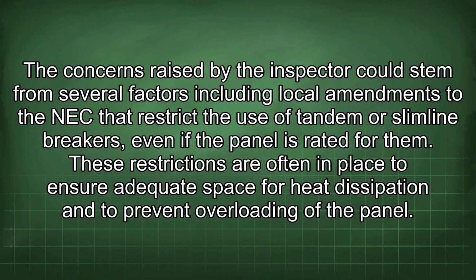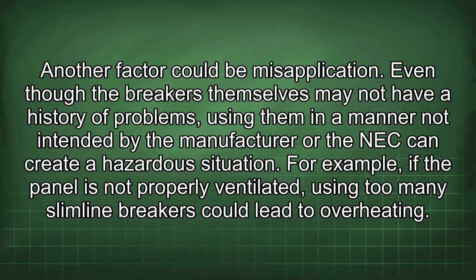The concerns raised by the inspector could stem from several factors, including local amendments to the NEC that restrict the use of tandem or slimline breakers, even if the panel is rated for them. These restrictions are often in place to ensure adequate space for heat dissipation and to prevent overloading of the panel. Another factor could be misapplication. Even though the breakers themselves may not have a history of problems, using them in a manner not intended by the manufacturer or the NEC can create a hazardous situation. For example, if the panel is not properly ventilated, using too many slimline breakers could lead to overheating.